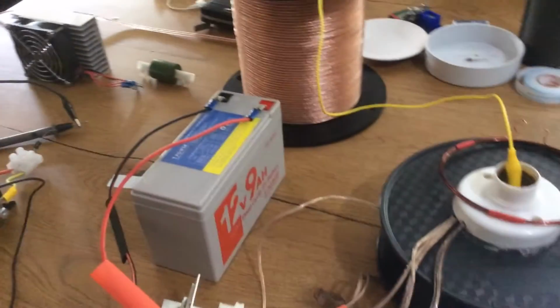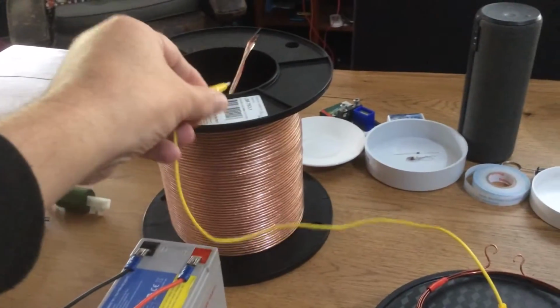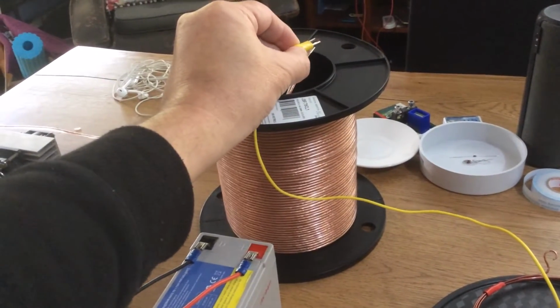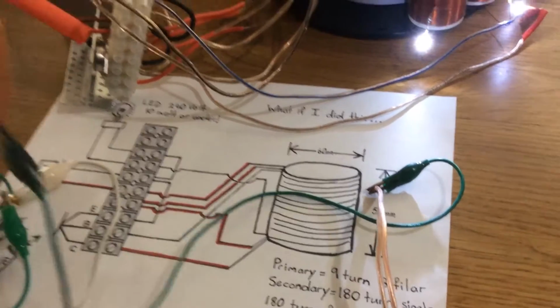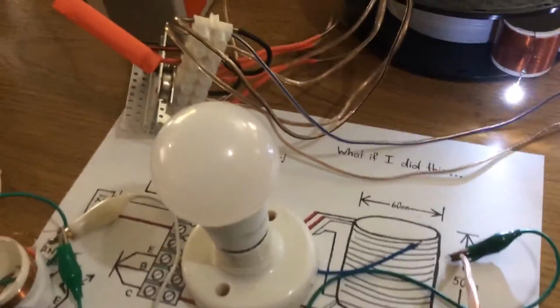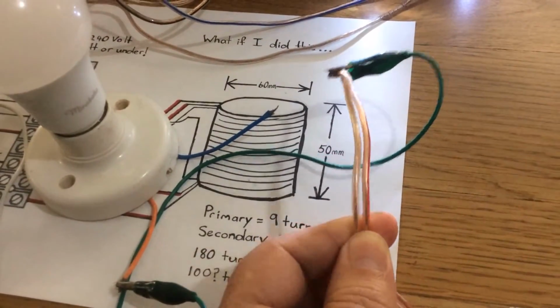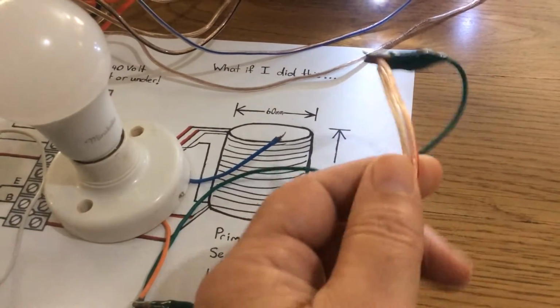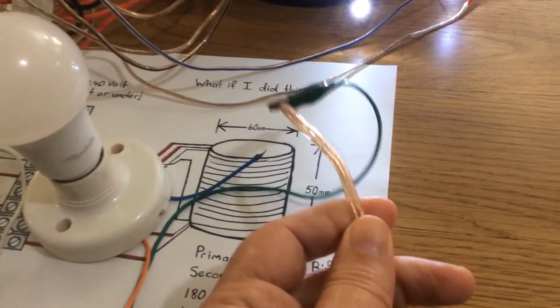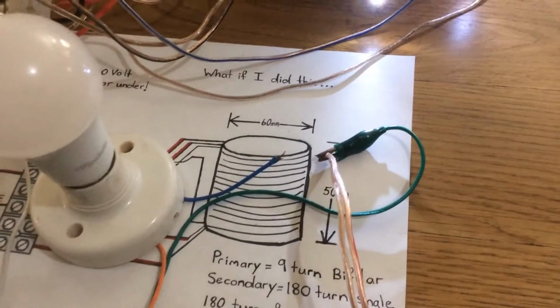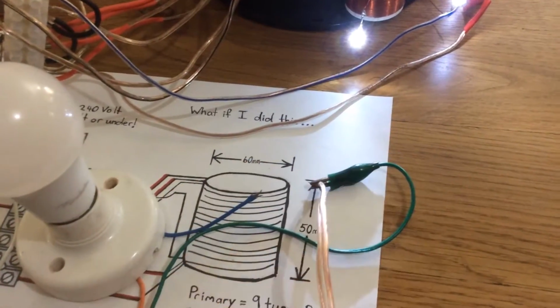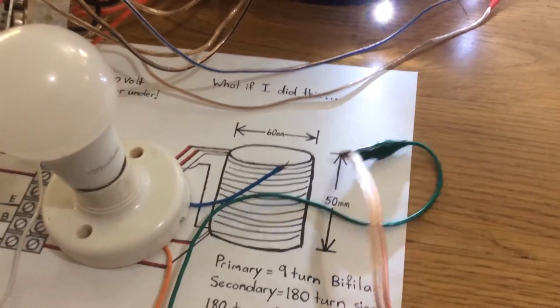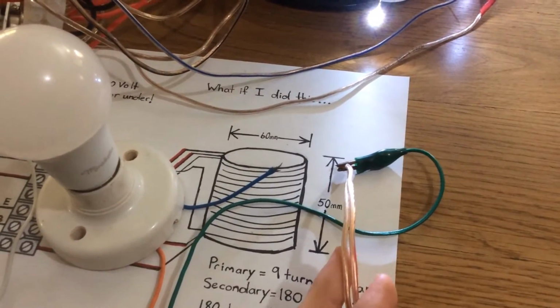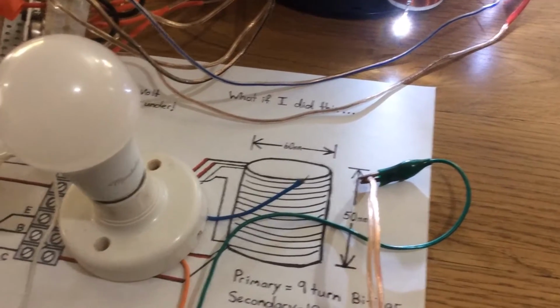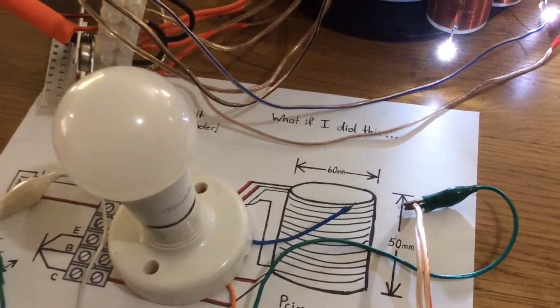So now let's take that earth connection and reconnect it, and repeat the same experiment. We've got earth number 2 — these earths are separated. We've got this one here, which is a 10 meter connection, two wires, but I've twisted them together at the end so that becomes one wire in essence, or two wires parallel, but it acts as one larger cable when you do that. That's 10 meters, and it goes into the ground, not very far down — only about a maximum of 10 centimeters into the ground.